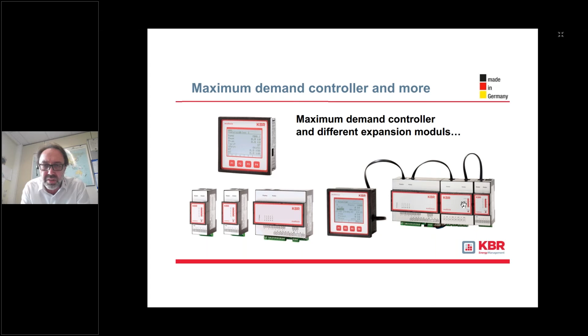Another system we have in our product range is our maximum demand controller. So if you have peaks in your consumption, by this controller, we have a trend calculation within the 15-minute period. This period is, of course, also flexible. We can also set a 30-minute period or a 1 hour period, depending on the demands in your country. But within this period, we can calculate a trend. And if the consumption would exceed the limit, we start to switch off defined loads by the relay modules. And by this action, we avoid these very expensive peak loads.